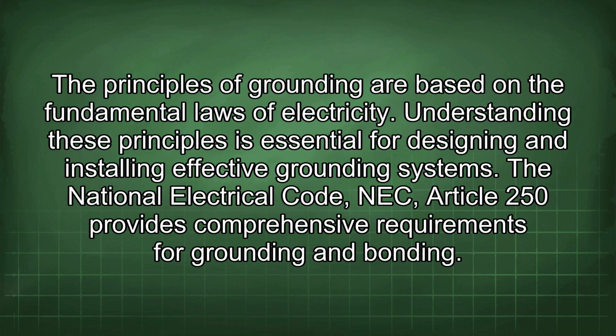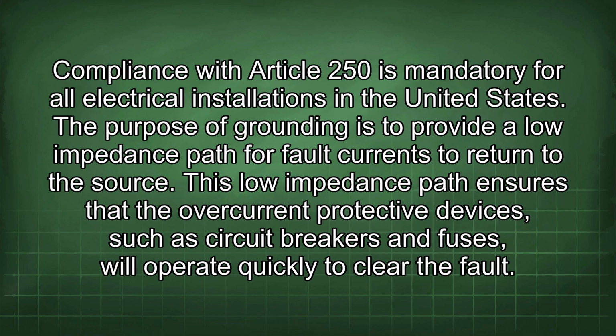The principles of grounding are based on the fundamental laws of electricity. Understanding these principles is essential for designing and installing effective grounding systems. The National Electrical Code (NEC) Article 250 provides comprehensive requirements for grounding and bonding. Compliance with Article 250 is mandatory for all electrical installations in the United States. The purpose of grounding is to provide a low-impedance path for fault currents to return to the source.